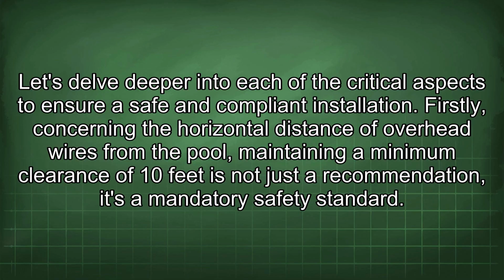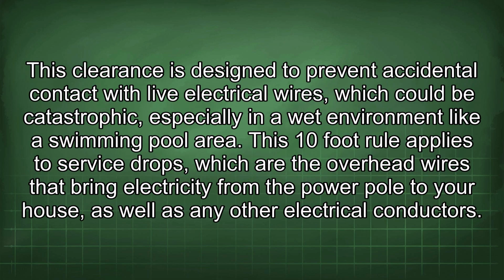Firstly, concerning the horizontal distance of overhead wires from the pool, maintaining a minimum clearance of 10 feet is not just a recommendation, it's a mandatory safety standard. This clearance is designed to prevent accidental contact with live electrical wires, which could be catastrophic, especially in a wet environment like a swimming pool area. This 10-foot rule applies to service drops, which are the overhead wires that bring electricity from the power pole to your house, as well as any other electrical conductors.